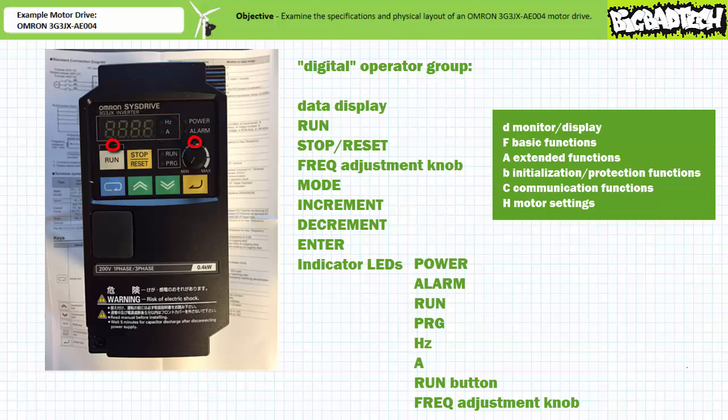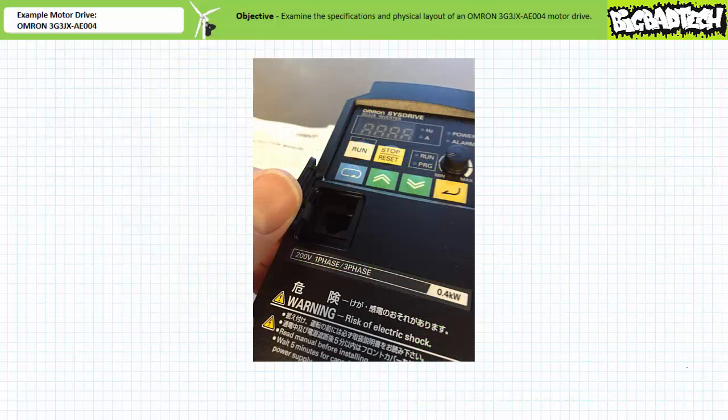Finally, the LEDs above the run button and the frequency adjustment knob are lit when the motor drive is programmed to allow manual direct operation using elements within the digital operator group. If these LEDs are not lit, the motor drive is under remote control. The front panel also includes an accessory RJ45 jack communications port under a cover.